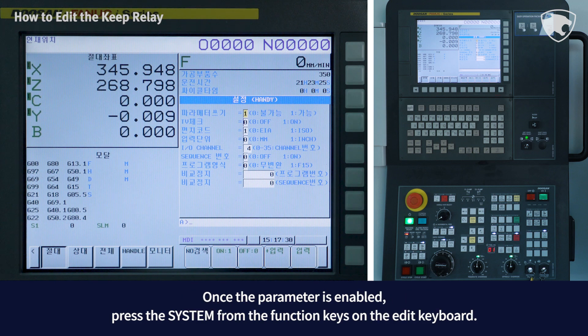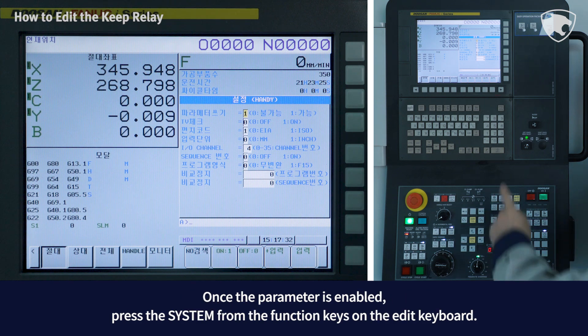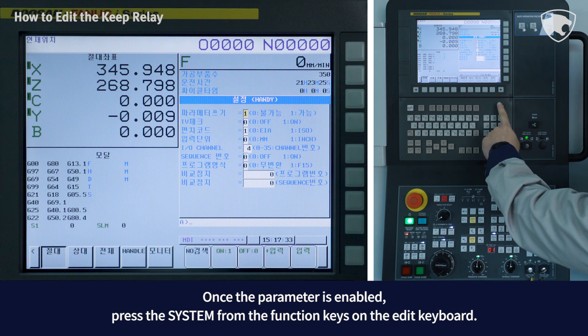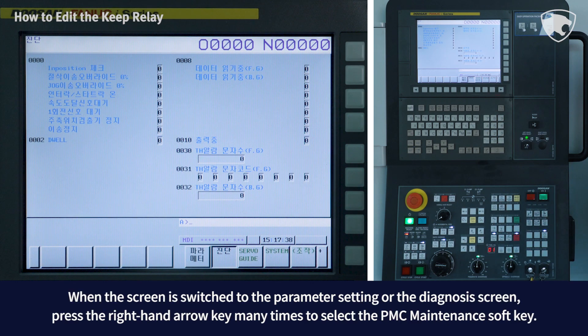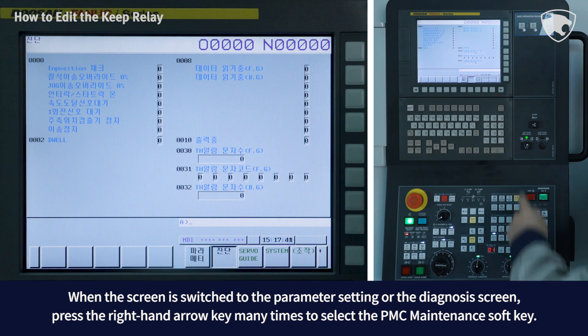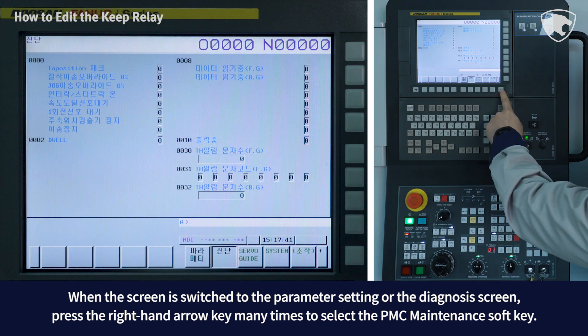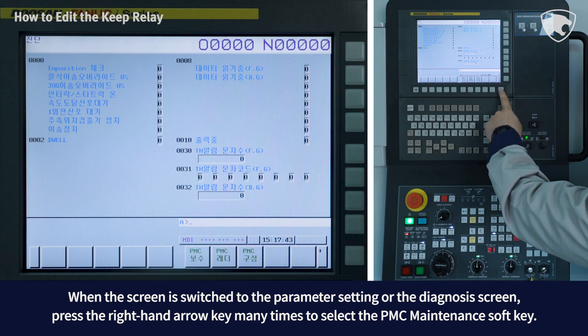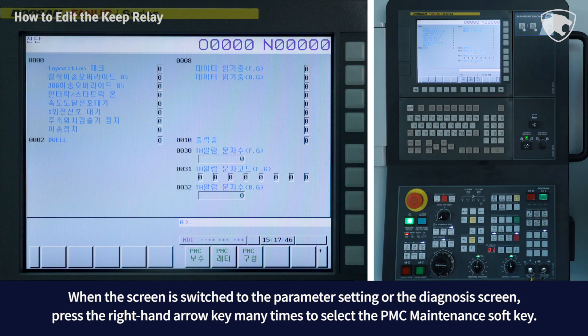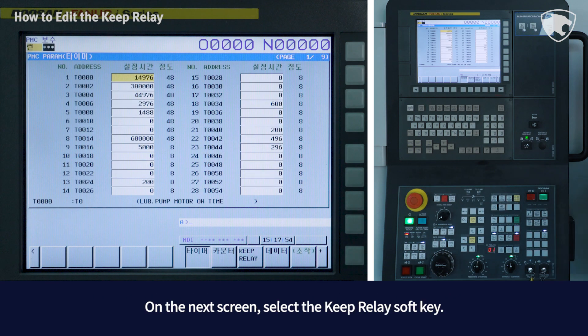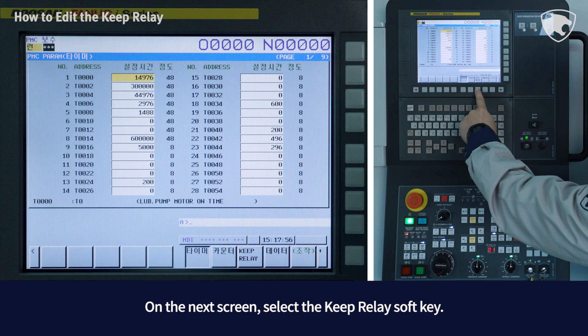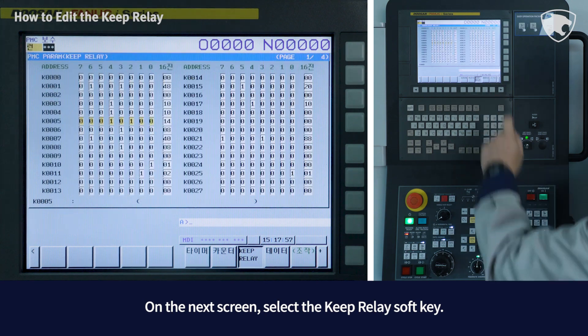Once the parameter is enabled, press the system key from the function keys on the edit keyboard. When the screen switches to the parameter setting or diagnosis screen, press the right-hand arrow key many times to select the PMC maintenance soft key. On the next screen, select the keep relay soft key.